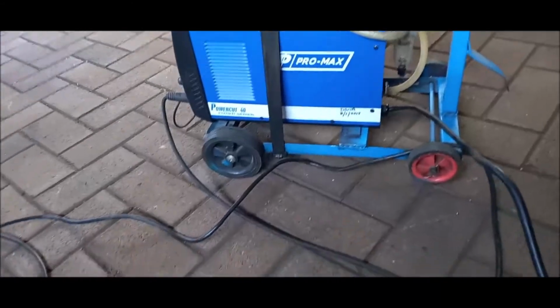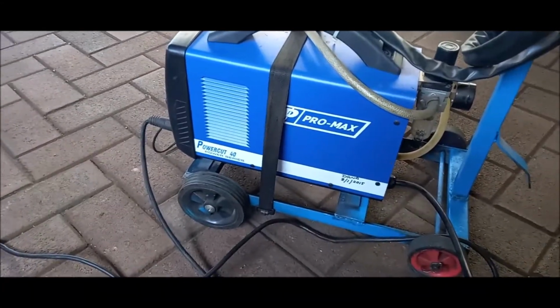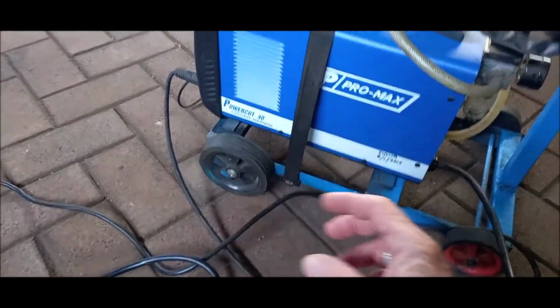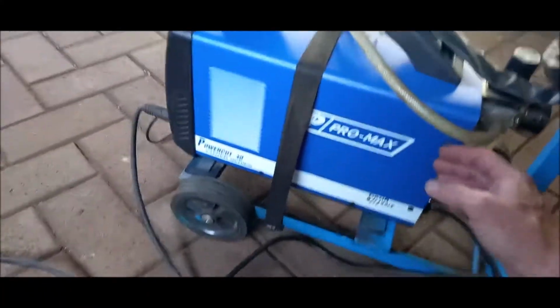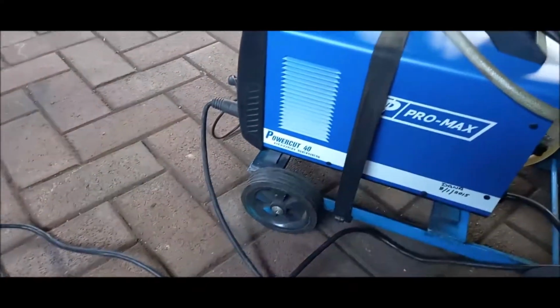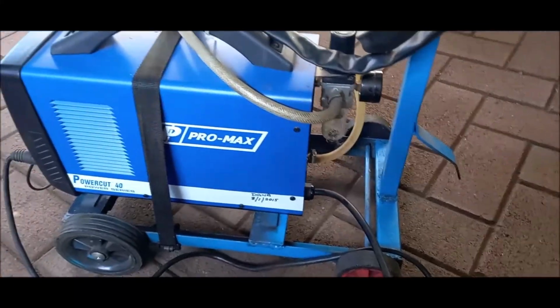In the next video I want to show you how to open this thing and clean it. It's necessary to clean it once in a while, to blow it out with air, because all the cuttings, the fine dust, metal particles go in here, get sucked in by the fan and get deposited over the IGBTs, like the field effect transistors that do all the switching here, and then they short out. We had quite a few at work that were already damaged. We had to buy new ones.